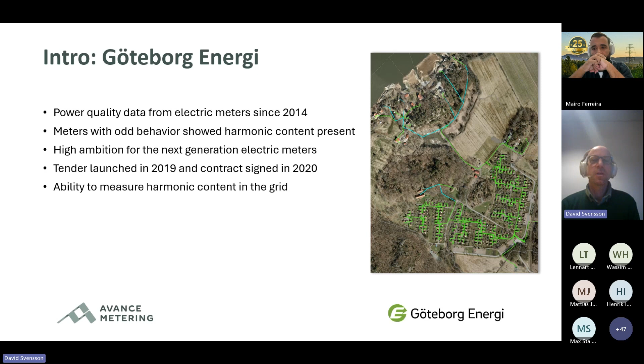Harmonics is the presence of unwanted frequency components. As you can see in the picture, it will affect the waveform for the voltage and the current. When harmonics are present, it can significantly impact the performance and reliability of a power system. To find a distorted wave, you need to use the total harmonic distortion, THDU, from an electric meter. It considers all harmonics present that the meter can calculate, not measure, but calculate. THDU will show the deviation in the voltage, and THDI will show the deviation in the current. We will focus on deviation in the voltage today, as it's what most new meters can register.